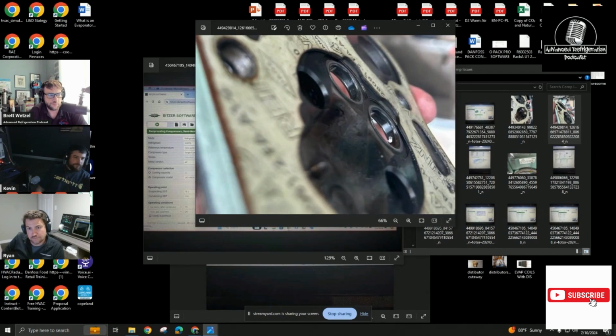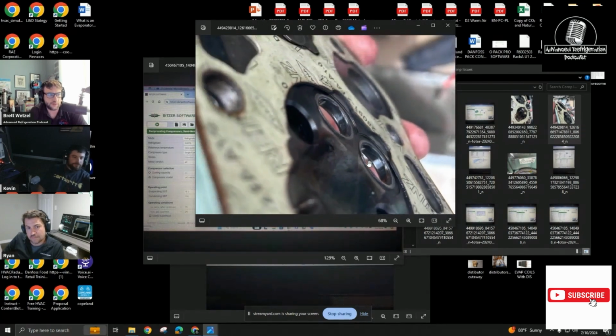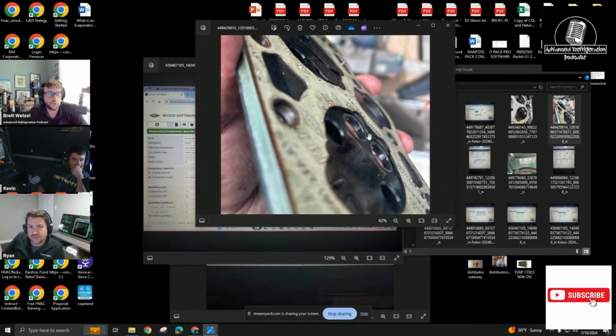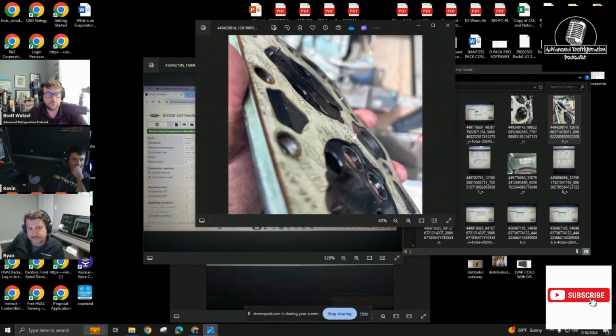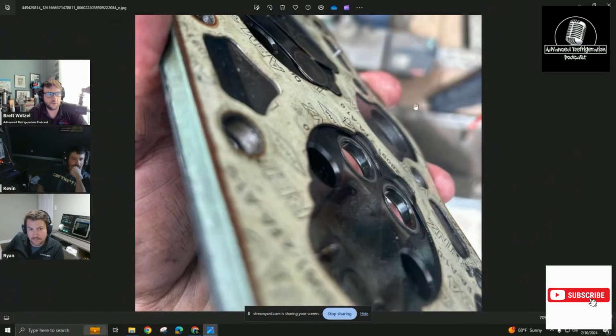Yeah, I don't know. This is why I'm such a big proponent of not doing pump down tests. Yeah, because you can still have that other valve hold, right? Yep. So like I said, trend of discharge superheat would be handy to have. Yeah, he doesn't have access to that, unfortunately. And that's one of the things with diagnosing, right? You can do a whole bunch of stuff if you have more information than really what you need, right? You were talking about diagnosing oil issues or whatever.